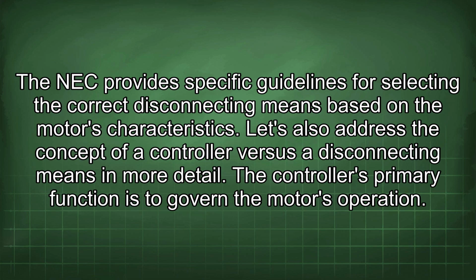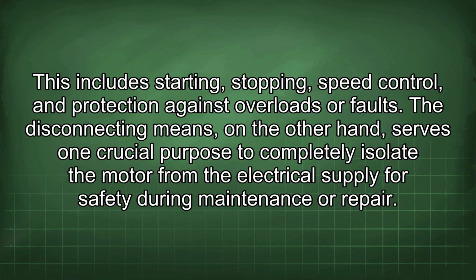Let's also address the concept of a controller versus a disconnecting means in more detail. The controller's primary function is to govern the motor's operation. This includes starting, stopping, speed control, and protection against overloads or faults. The disconnecting means, on the other hand, serves one crucial purpose: to completely isolate the motor from the electrical supply for safety during maintenance or repair.